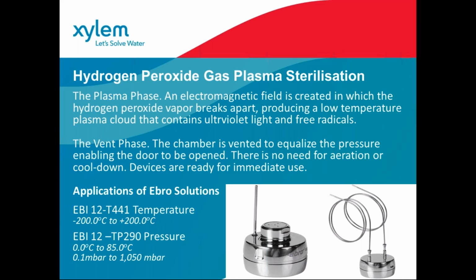Okay, in the plasma phase, an electromagnetic field is created to produce low temperatures, a cloud that contains ultraviolet lights, or UV lights, and free radicals. The vent phase must be measured because the chamber needs to have an equilibration between pressure and temperature. This will enable the door to be opened safely.